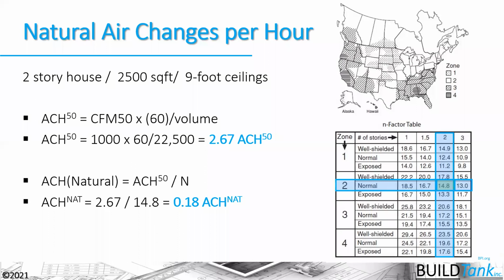You can see the air change number is quite different than the natural air change number. First, it's a whole number, not a decimal. So you have to gain some type of frame of reference for what you're looking at. 0.18, is that an actually tight house, or is it a house that is close to the requirement by the code? In this case, 0.18 equals 2.67 air changes per hour. Well, that's really almost the minimum requirement for the code in Climate Zone 5 here in Colorado.